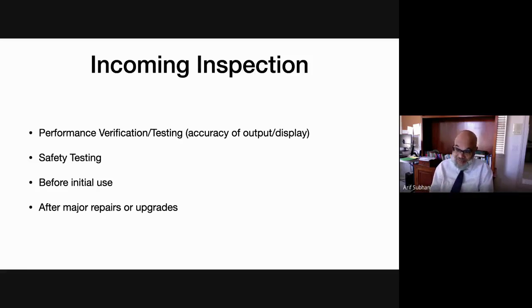And some of you may have seen, there are a lot of simulators that we have for testing different types of devices. And they simulate, like, the heart, and you see whether it's giving accurate information. And that's also always within the tolerances of the specification, plus or minus whatever the number is. Plus or minus 1%, 2%, whatever the standards call for or the manufacturer calls for. Safety testing, obviously, very, very essential.